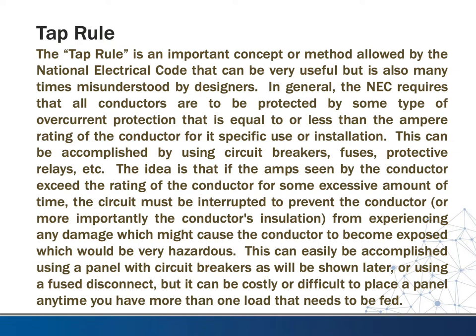So we want to talk about the tap rule. The tap rule is an important concept or method allowed by the National Electrical Code that can be very useful, but is also many times misunderstood by designers. In general, the National Electrical Code requires that all conductors are to be protected by some type of overcurrent protection that is equal to or less than the ampere rating of the conductors for its specific use or installation. This can be accomplished by using circuit breakers, fuses, protective relays, etc.